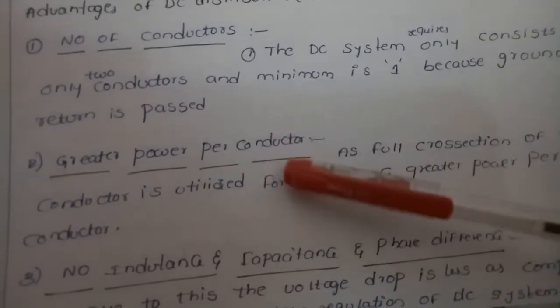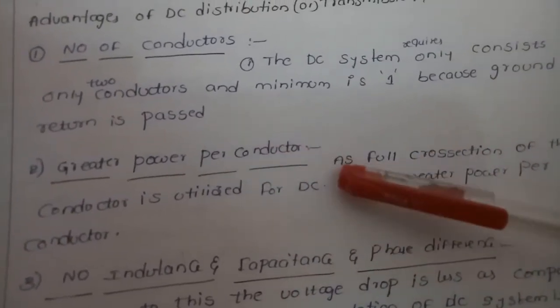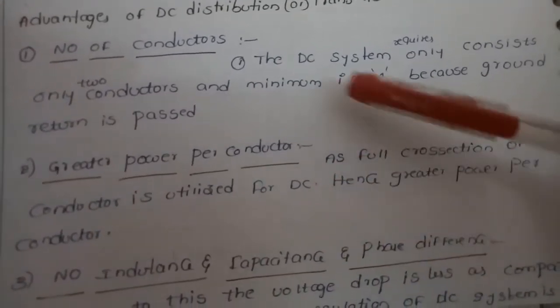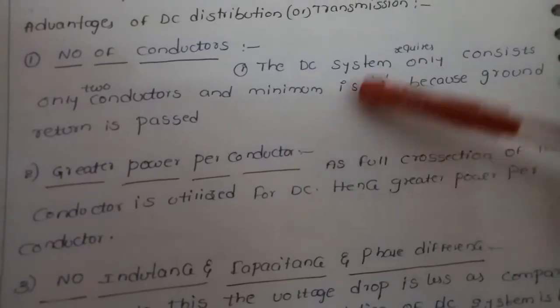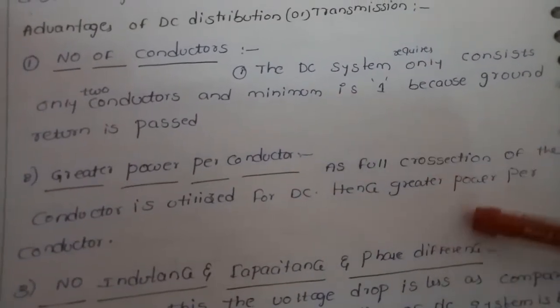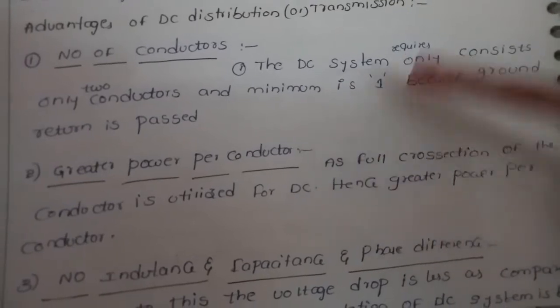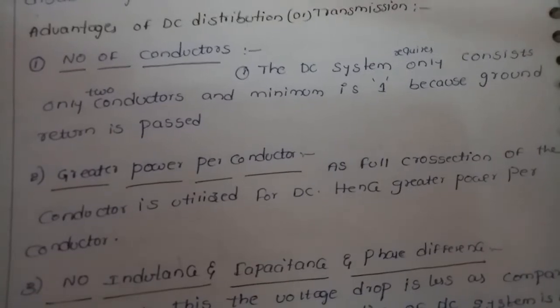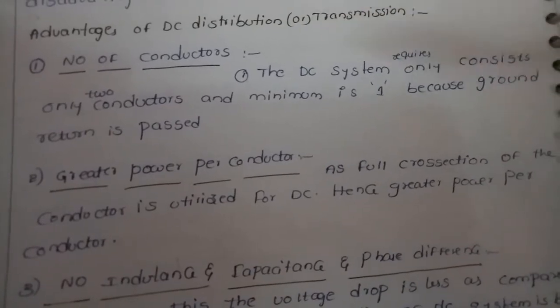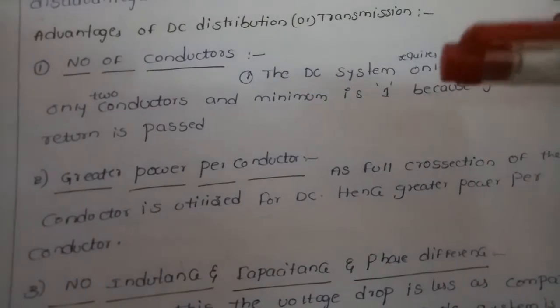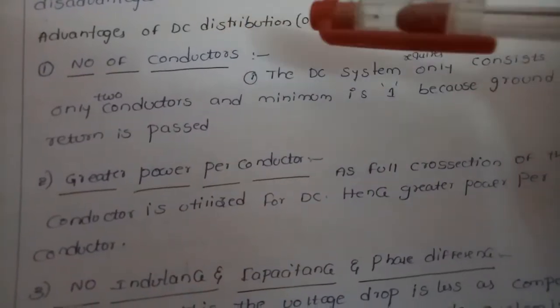Another advantage of DC distribution is greater power per conductor, because the full cross-section of the conductor is utilized for DC. In AC systems, due to the skin effect, only the outer surface of the conductor carries current, so less power per conductor is available compared to DC.